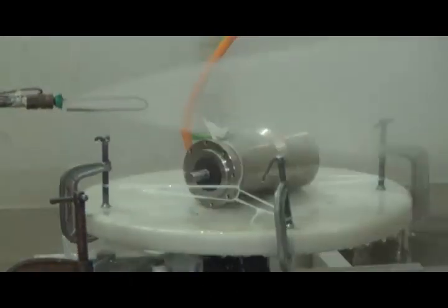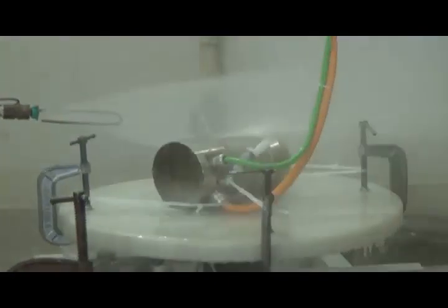Our MPW motors were subjected to water intrusion tests, as specified in DIN 40050, Part 9, Section 7.4, at a level of protection of IP69K. The motors were subjected to pressures up to 10,000 kPa and a temperature up to 80 degrees Celsius. Post-test inspection of the motors found no evidence of internal or external damage from water. Details can be found on the MPW product page on parkermotion.com.